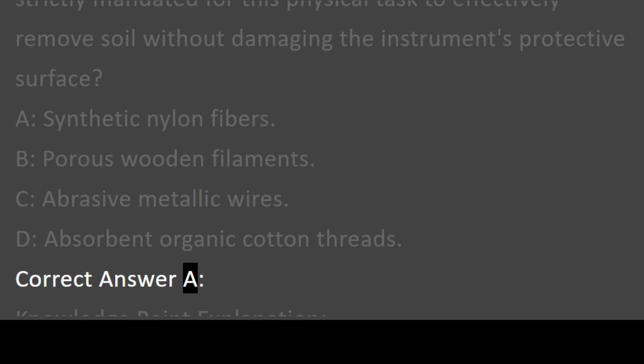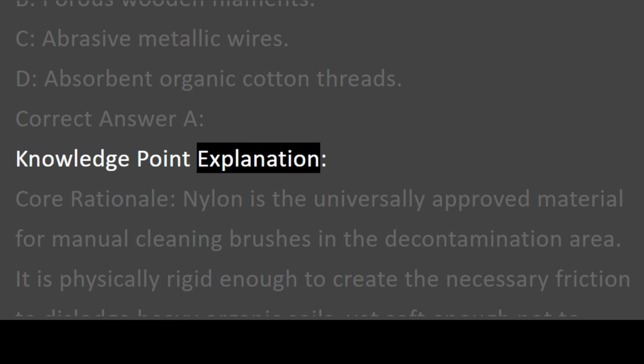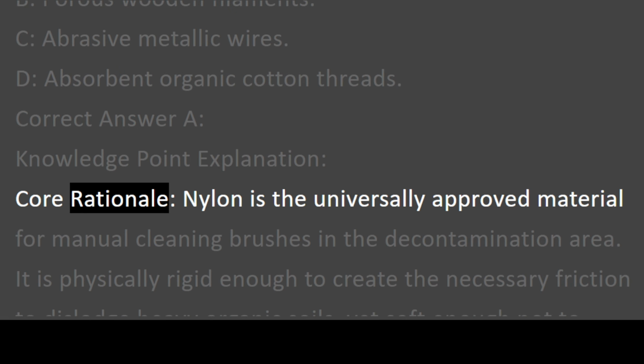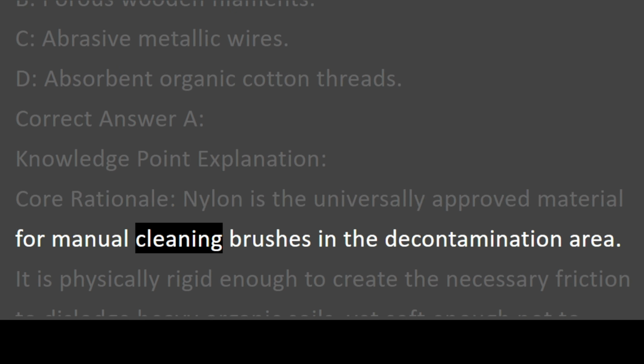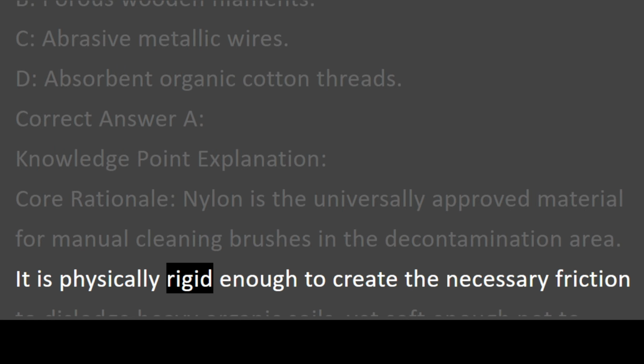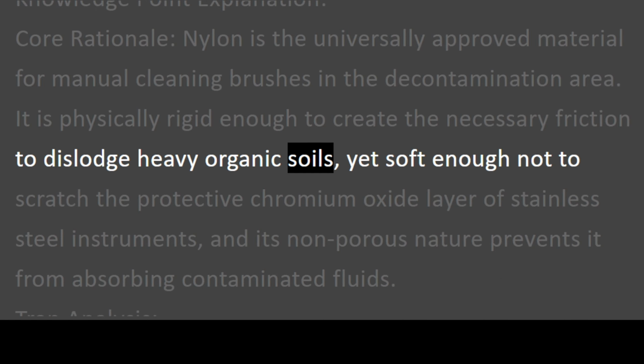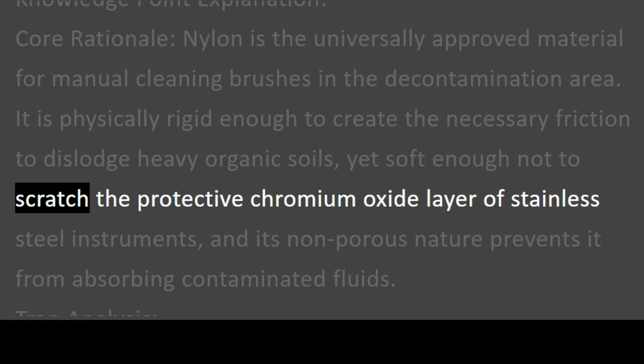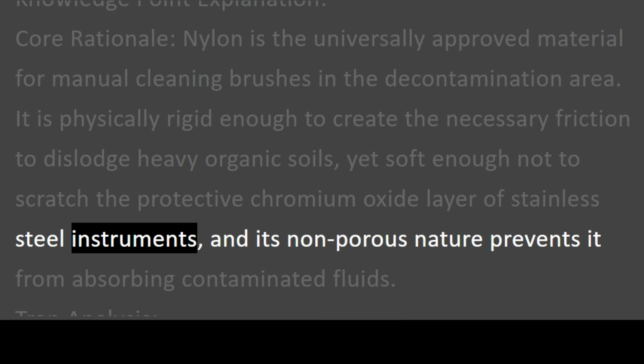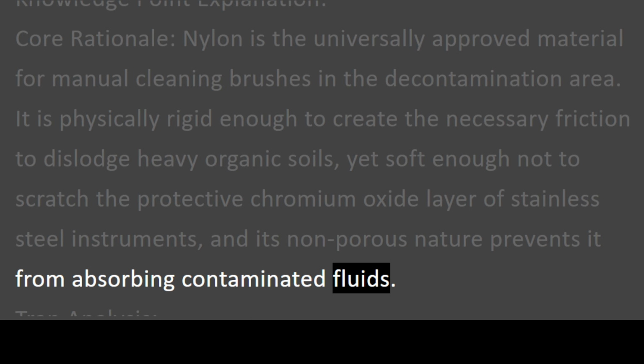Correct answer A. Knowledge point explanation. Core rationale. Nylon is the universally approved material for manual cleaning brushes in the decontamination area. It is physically rigid enough to create the necessary friction to dislodge heavy organic soils, yet soft enough not to scratch the protective chromium oxide layer of stainless steel instruments, and its non-porous nature prevents it from absorbing contaminated fluids.